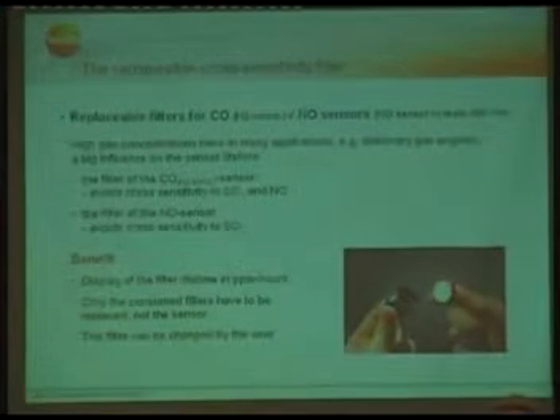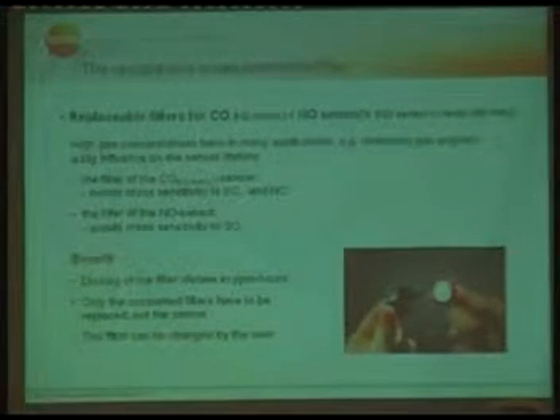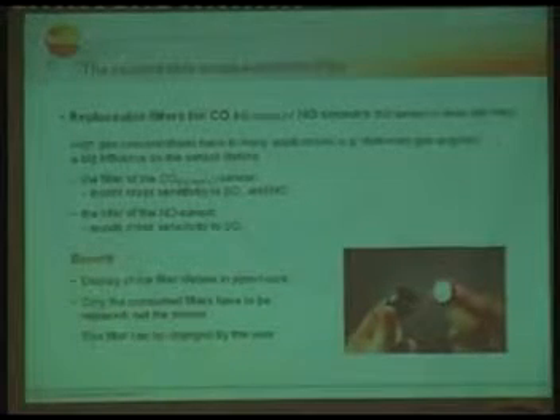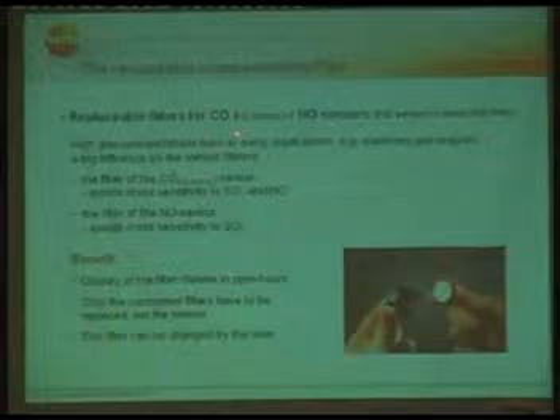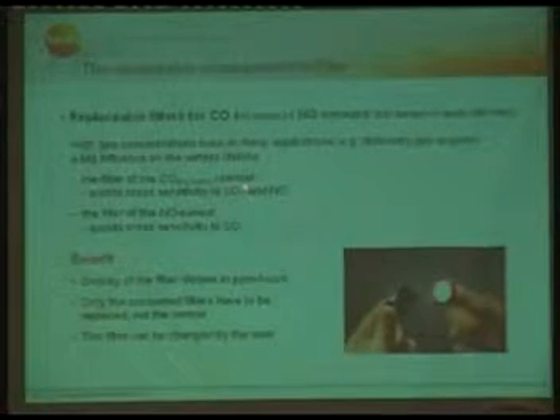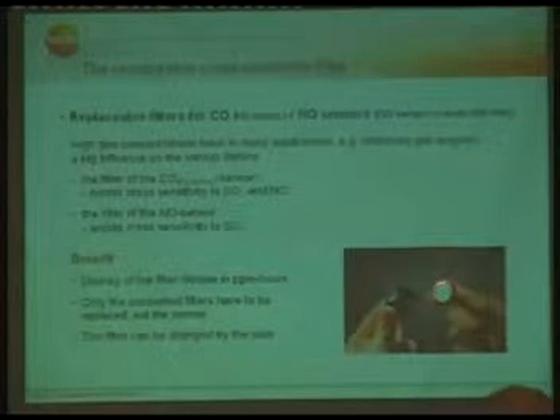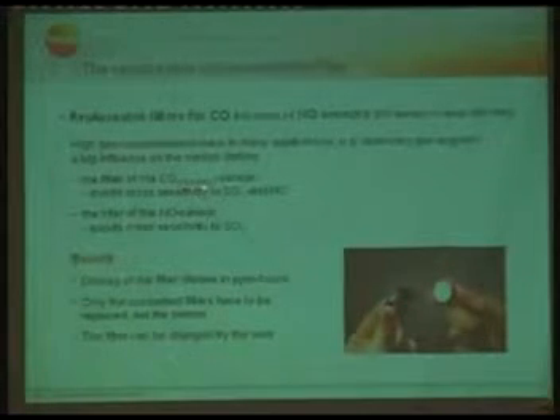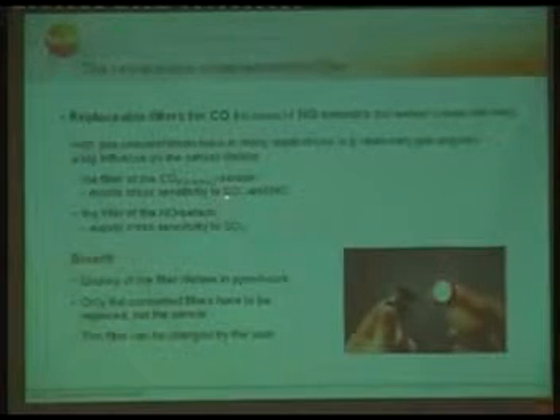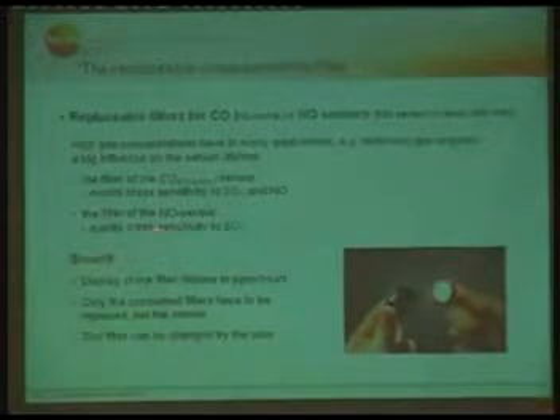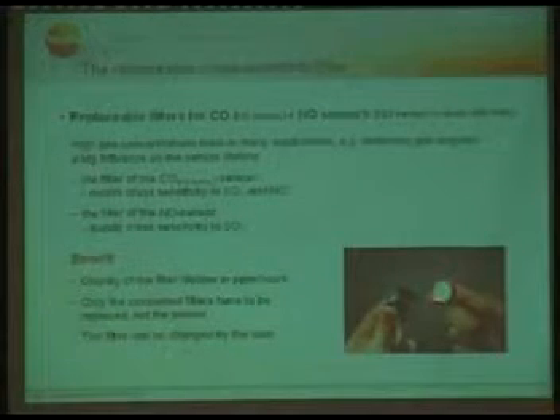It's just putting sensor in, and that's it. Okay, sensor replacement, I mentioned a few times before, just removing the sensor, putting the new one in. The only tool required is your hand, and no test gas as well. Then we have also new filters, which are in the TESTO 340 and 350. The CO sensor and the NO sensor, they have a small filter, a cross-sensitivity filter. With the CO sensor, it avoids cross-sensitivity to SO2 and NO. And the NO sensor avoids cross-sensitivity to SO2, this little filter.